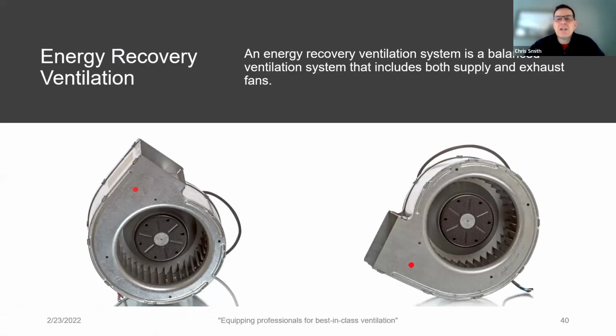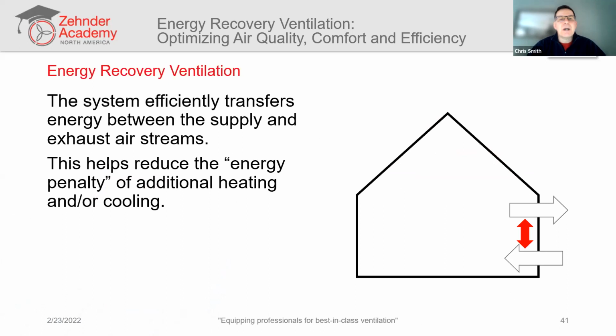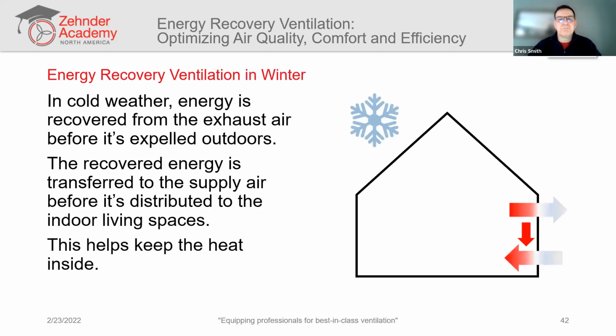An energy recovery ventilation system is basically a balanced ventilation system that includes both the supply and exhaust fan. That's the starting point. We've already acknowledged that, but we want to find some way of achieving the ventilation or the energy recovery. What we're going to do is find some way of efficiently transferring energy between the supply air and the exhaust air. So we're pulling air into the building and we're exhausting air out of the building. How do we change energy between those air streams?